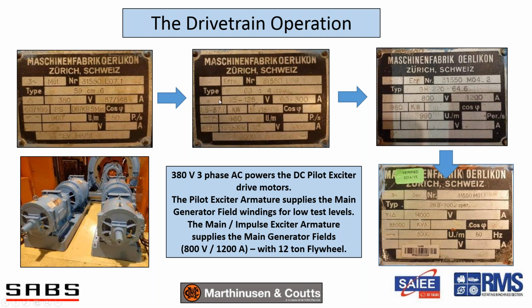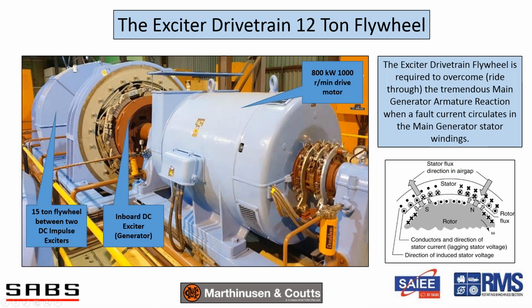There are also two pilot exciters for lower currents, driven by 380 volt 3-phase AC motors. That's the nameplate of the AC motor. But the main function is really the main exciters, which are effectively just DC generators producing 800 volts at 1200 amps, supported by the 12-ton flywheel. Here's a little bit of what it looks like.